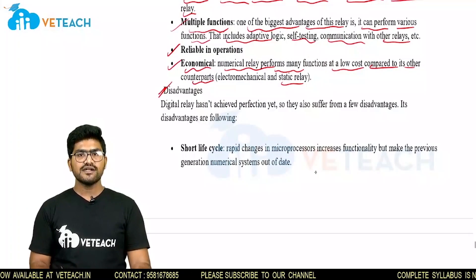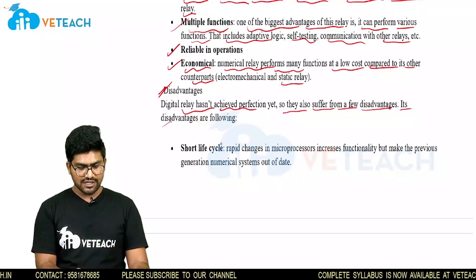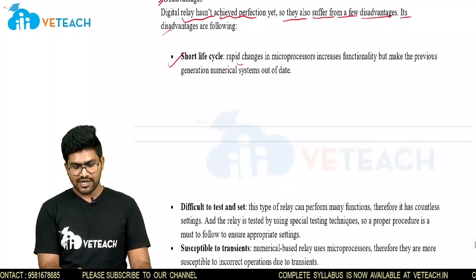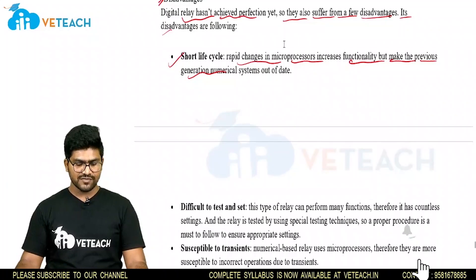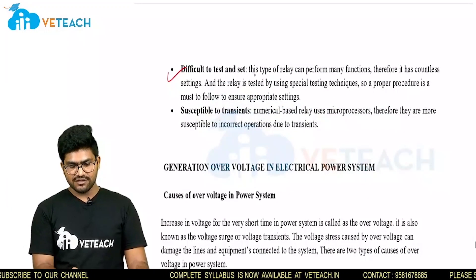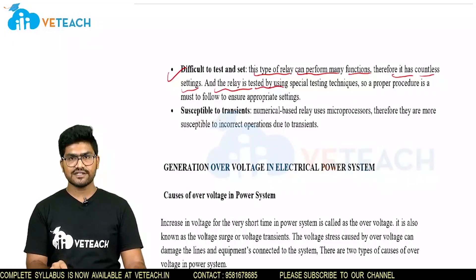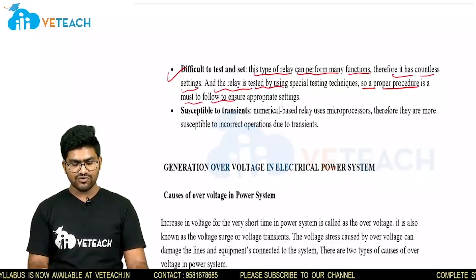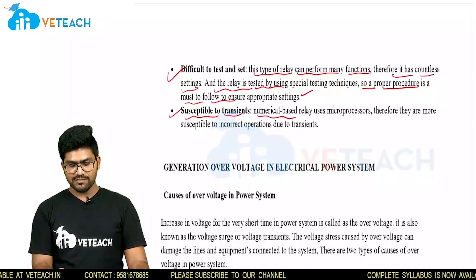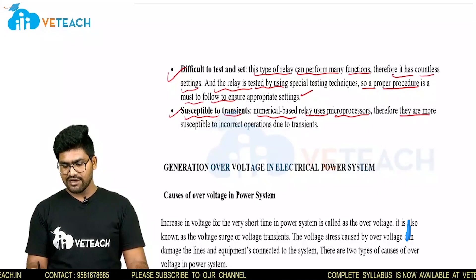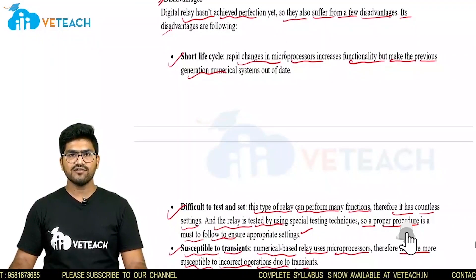Coming to disadvantages — digital relays have not achieved perfection yet and suffer from a few disadvantages. The first is short life cycle: rapid changes in microprocessor technology increase functionality but make previous generation numerical systems outdated. Next is difficult to test and set — this type of relay can perform many functions, therefore it has countless settings and the relay is tested using special testing techniques; a proper procedure must be followed to ensure appropriate settings. The last disadvantage is susceptibility to transients: numerical based relays use microprocessors, and therefore they are more susceptible to incorrect operation due to transients. This concludes the topic on numerical relays. Thank you.